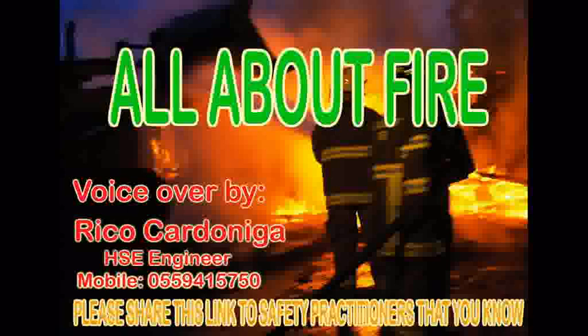Class B2 fire, which involves liquids not soluble in water, such as petrol and oil. These can be extinguished by using foam, carbon dioxide, dry powder, light water, and vaporizing liquid.